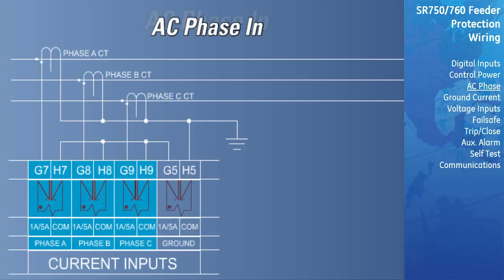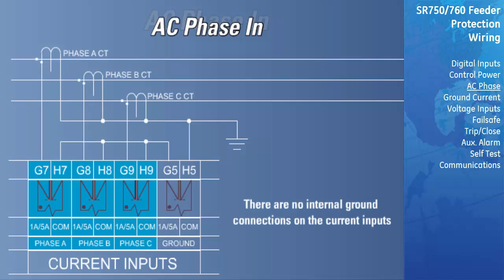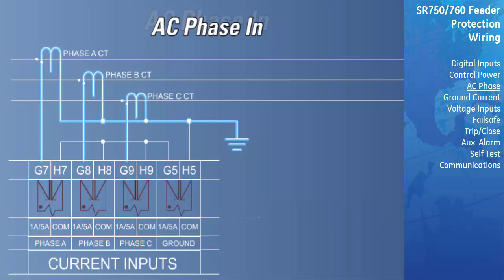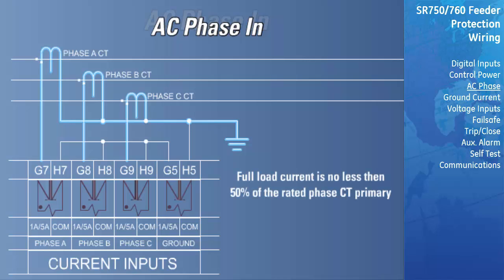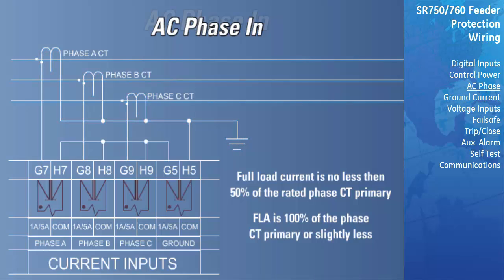There are 3 channels for phase current inputs, each with an isolating transformer. There are no internal ground connections on the current inputs. Each phase CT circuit is shorted by automatic mechanisms on the relay case if the unit is withdrawn. The phase CTs should be chosen such that the full load current falls between 50 and 100% of the rated phase CT primary. Ideally, the phase CT primary rating should be chosen such that the full load amps is 100% of the phase CT primary or slightly less, but never more. This will ensure maximum accuracy for the current measurements.